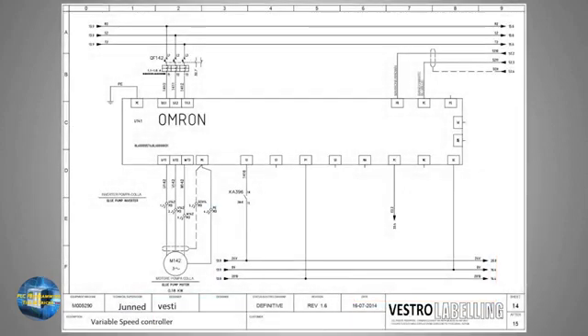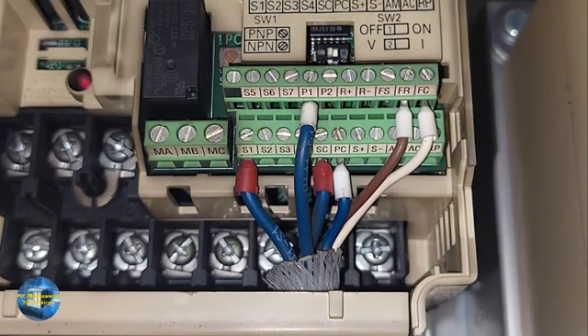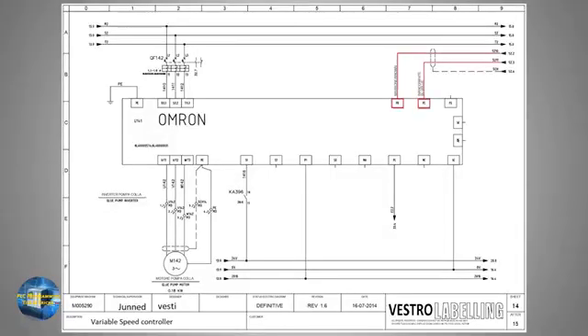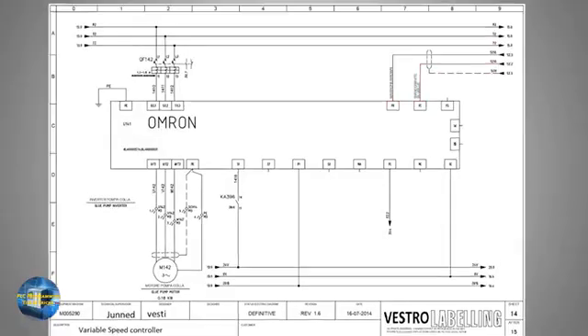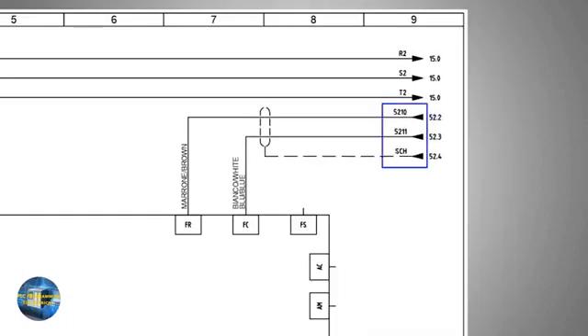We know that the VFD gets an analog speed reference signal from the PLC to control the RPM of the motor. The VFD has two wires connected at the FC and FR terminals. These terminals are the analog input of the VFD. If you see the drawing, these two wires have tags S210 and S211, and these wires or lines have an arrow symbol at the starting point. 52.2 and 52.3 are mentioned near these arrows.